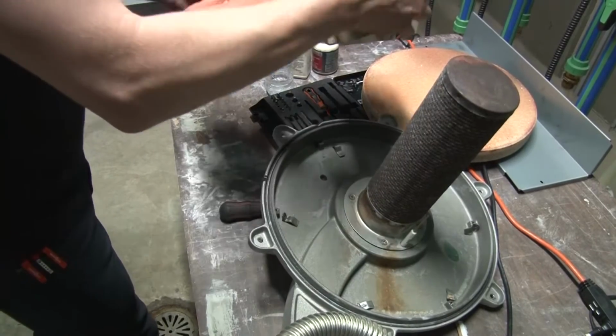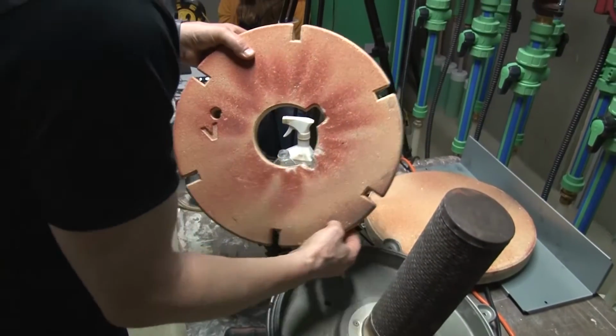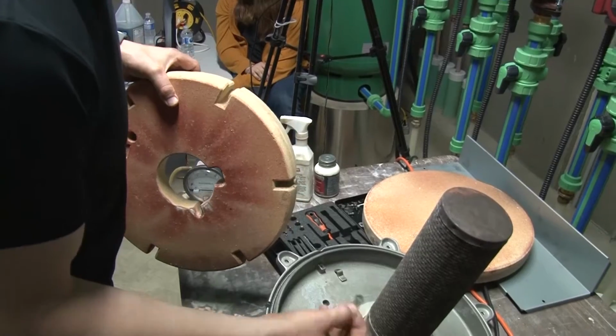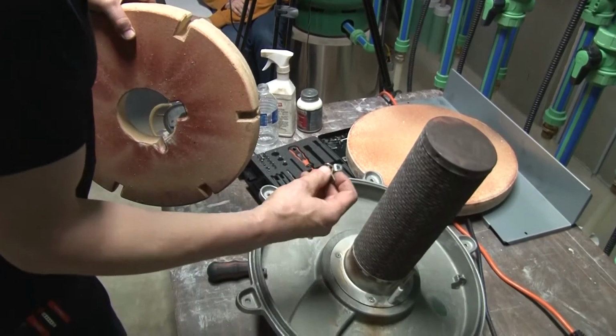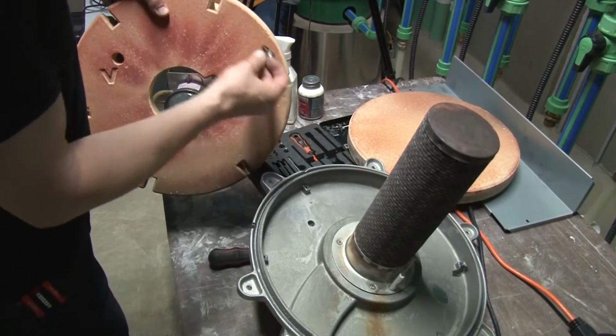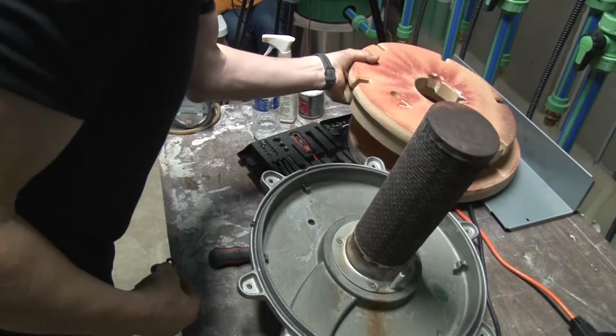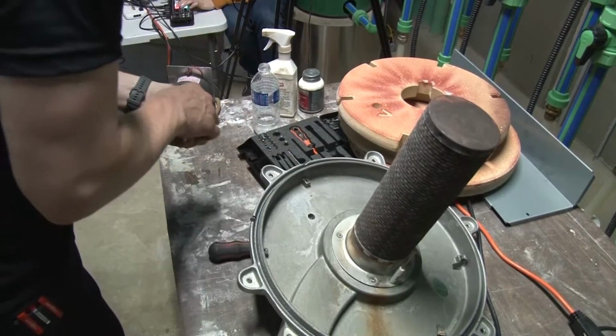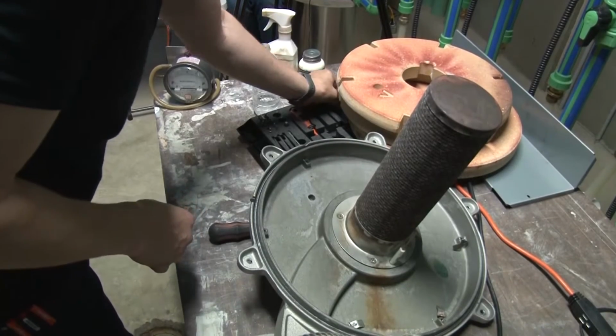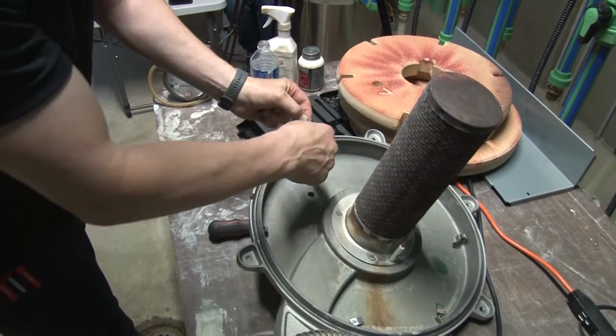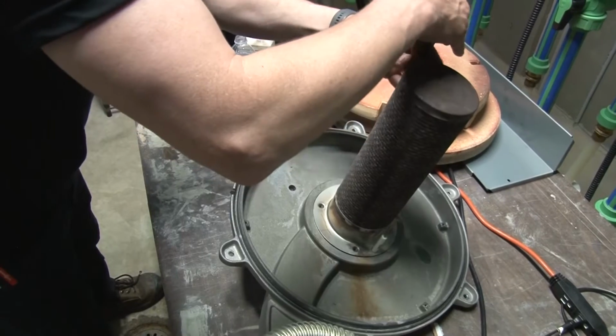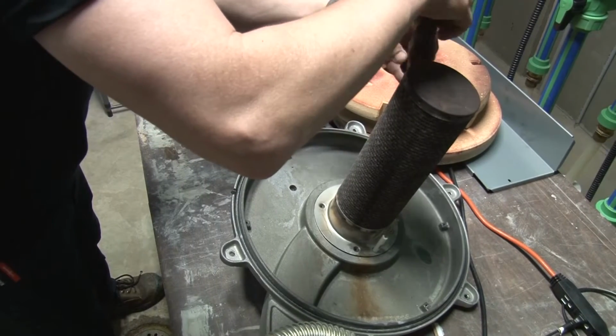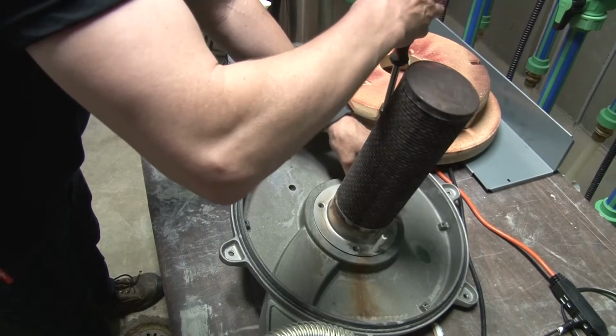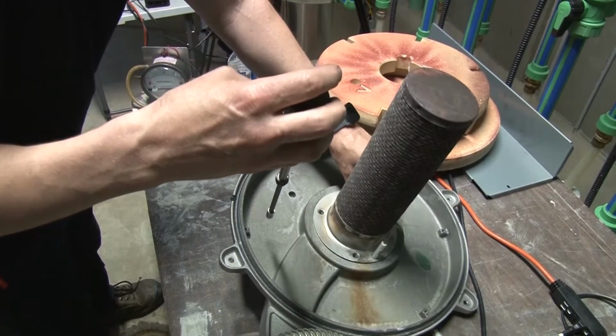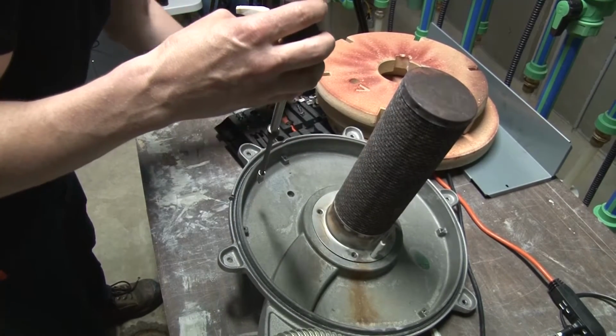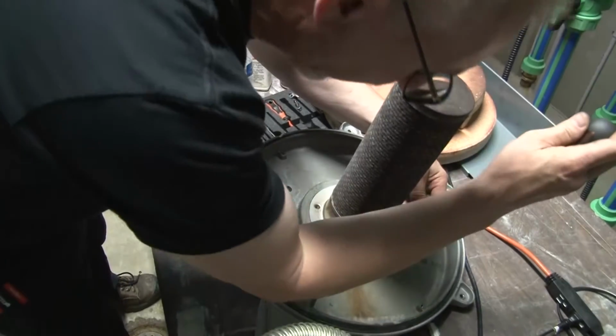But basically this little refractory is sealed down onto our burner flange with these little clips, one per little slot here. And we have these little 4mm bolts. You'll see me put them back in and they secure down on there. I put these little screws in an area that they're not going to fall down because you need to make sure that you don't have 3 of the 4 bolts and say, well, that ain't bad. You need to make sure you have all the bolts.